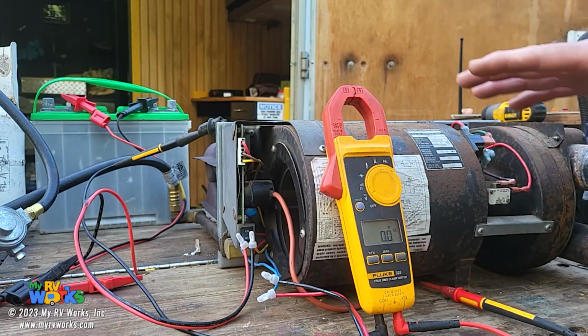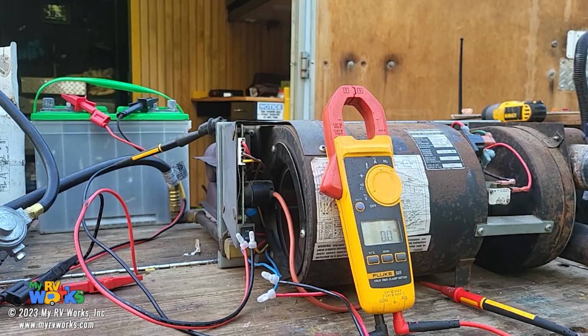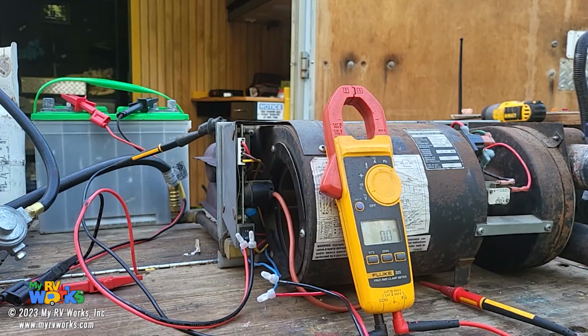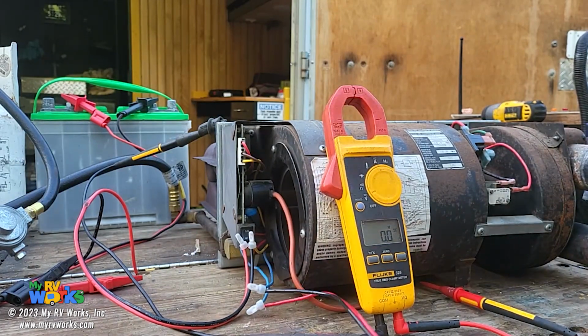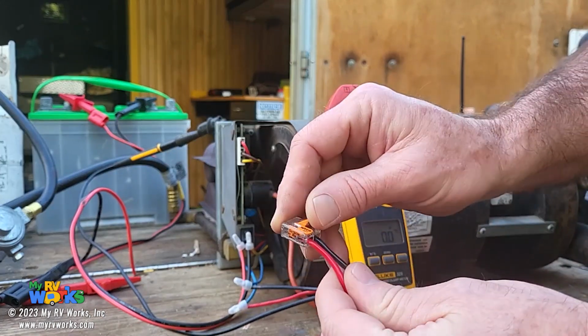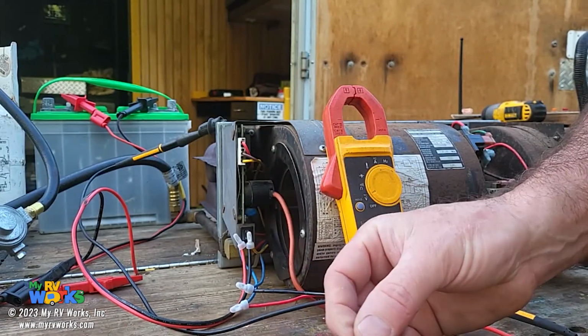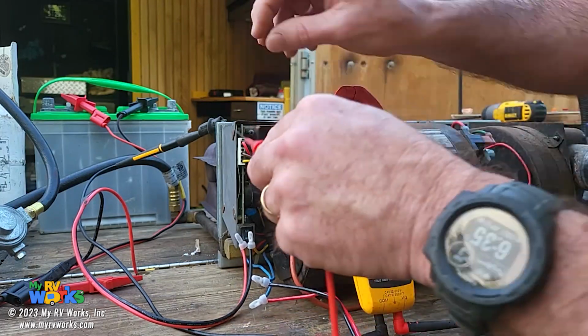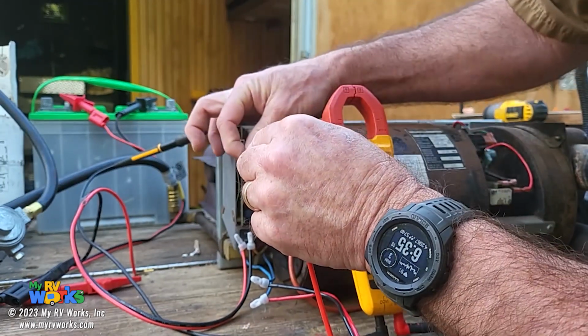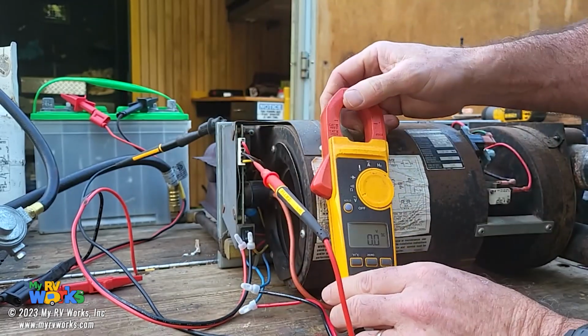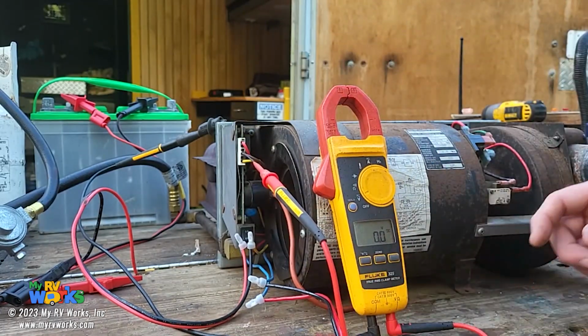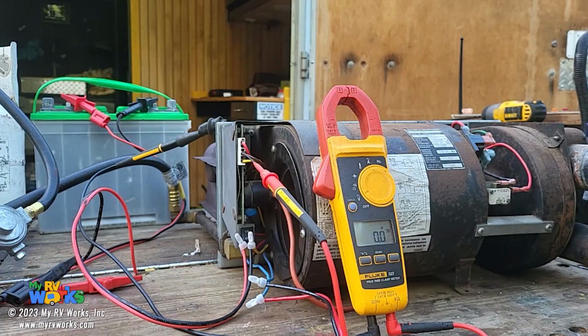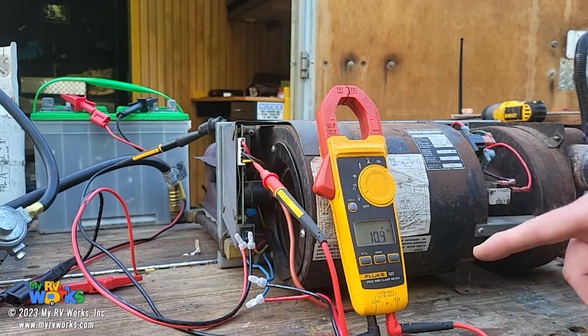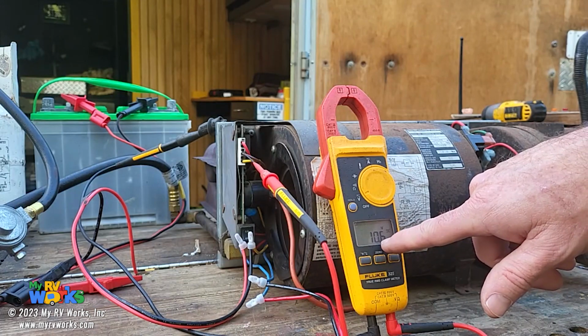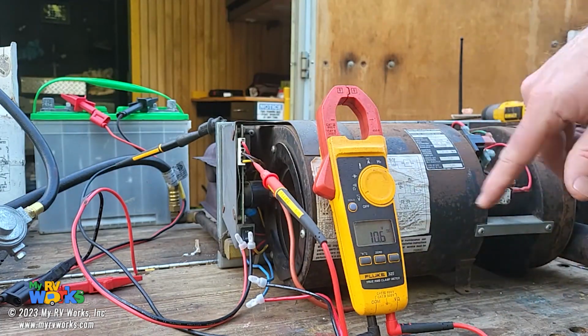So what I want to do now is turn on our propane cylinder, okay? And the furnace still won't start, because remember, it's in lockout. And what did we say was the way to clear a lockout situation? This is representing our thermostat, so I'm going to disconnect our thermostat, okay, and I'm going to reconnect our thermostat. And let's go into the brown wire here. There we go, okay. And everybody see the meter? Yeah. So, the meter good? There's a glare, but anyway. So, there it goes. There's my coil voltage going to my board, and I'm shooting a signal.